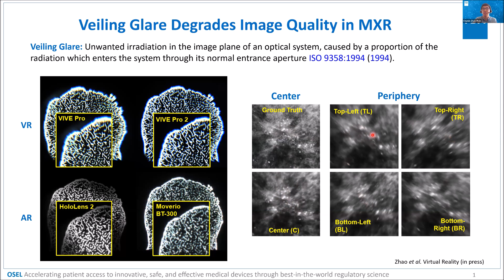field of view. For example, if I put the medical image at the center, here is a microcalcification for mammography. It looks pretty good, but if you move it towards the periphery, you can see how veiling glare can affect the image quality. To test it, we developed this test method using this white disk with a central black dot pattern. So theoretically, the luminance at the center should be 0, but because of veiling glare, you can measure the luminance at the center, which is associated with the glare.